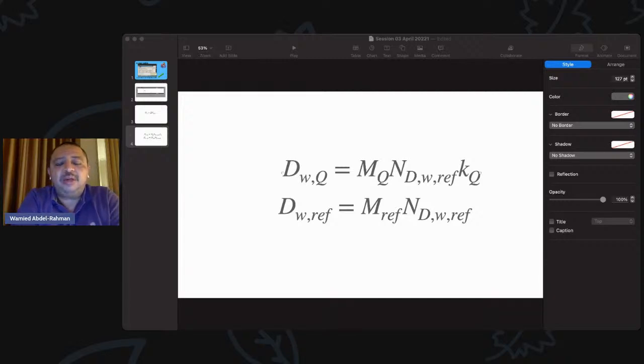One example I've shown is KQs. You can use Monte Carlo to determine the KQ, let's say, for our chamber design. Of course, if you have a cylindrical Farmer chamber, then you would probably need a different code, such as EGSnrc's egs_chamber, to simulate that complex geometry of the chamber. But the concept is the same.